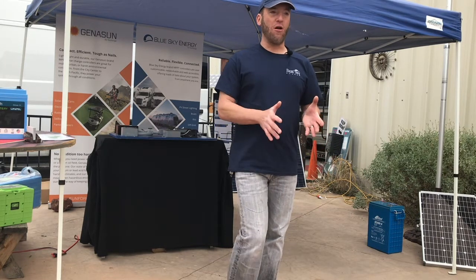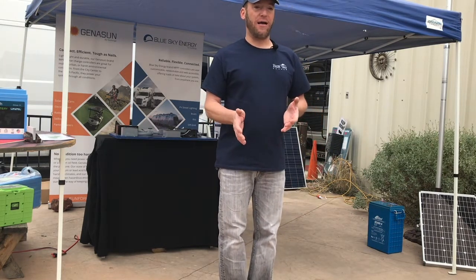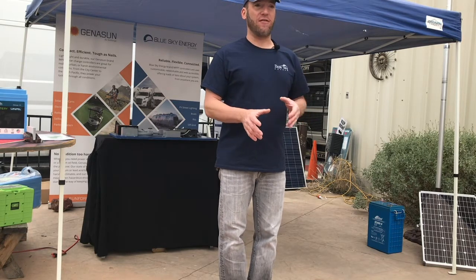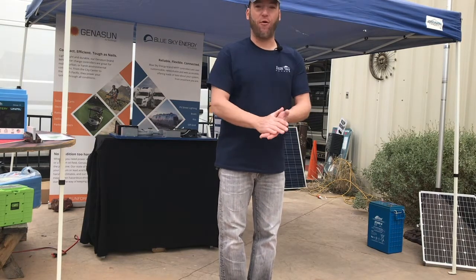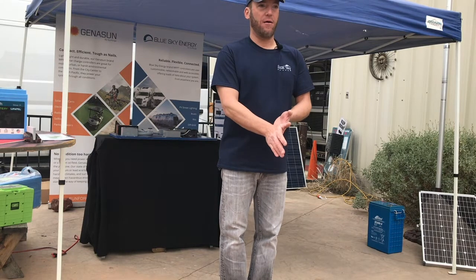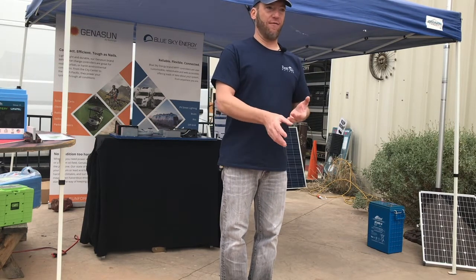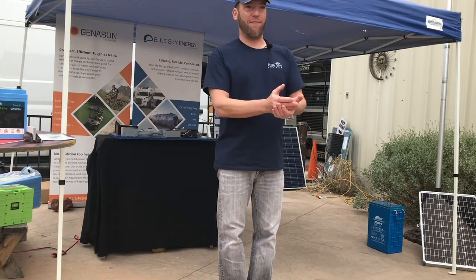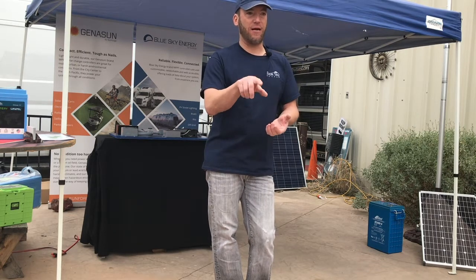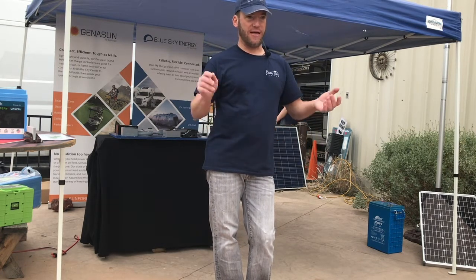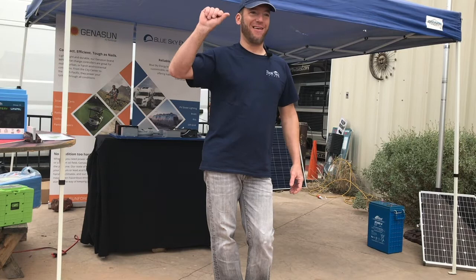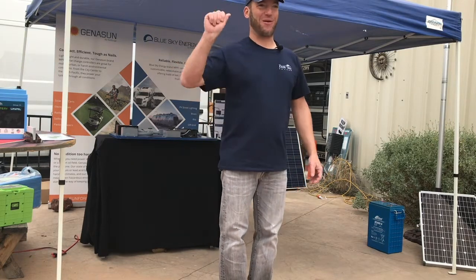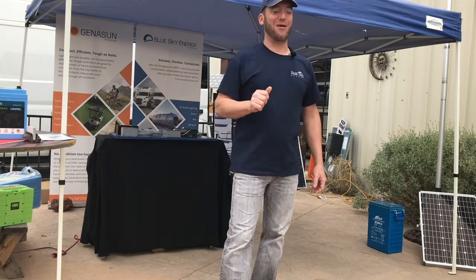It's more important when you get to DC breakers. Regular fuses don't blow right at their rating—if you have a 40 amp fuse, it's not going to blow at 41. But DC breakers, if you have a 40 amp breaker running at 40, can get hot and continually trip on you, just like any residential panel. You're like, darn it, I need a shorter extension cord or a thicker one because you're drawing too much power out of it.